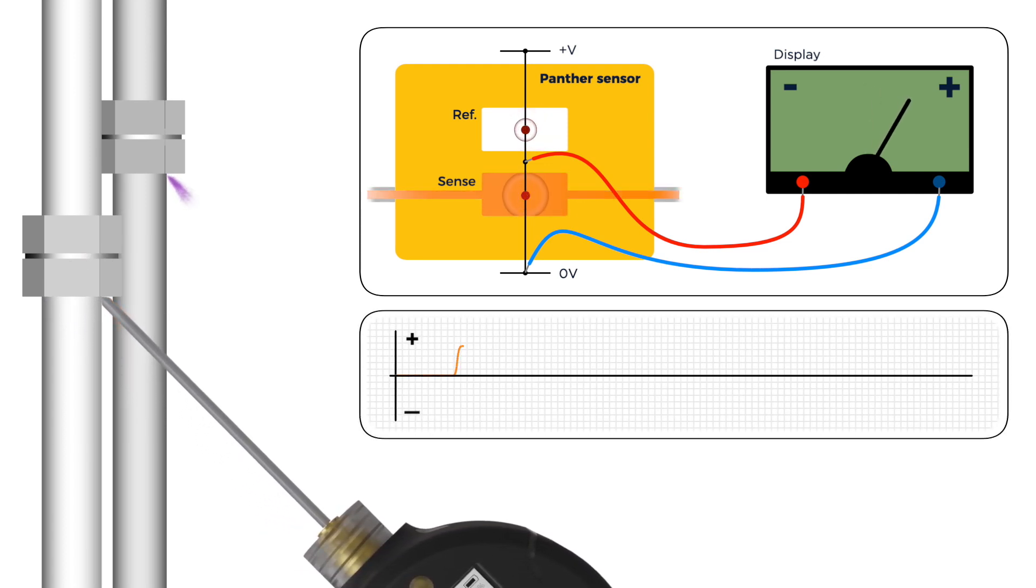It is this change in temperature and the resulting change in the thermistor's resistance that is measured and converted to a leak rate. Some gases are more thermally conductive than air and others are less conductive.